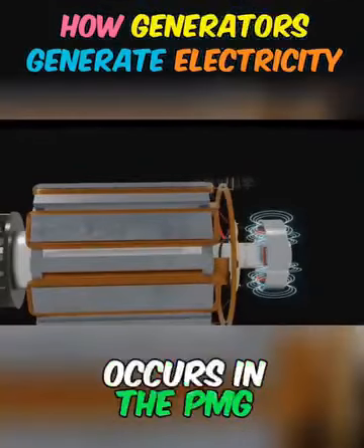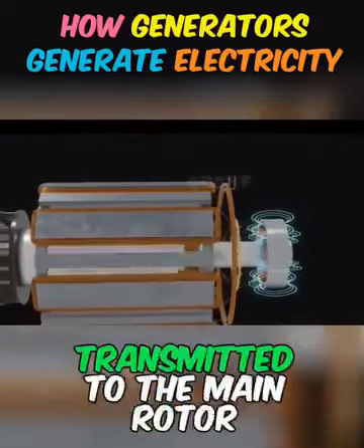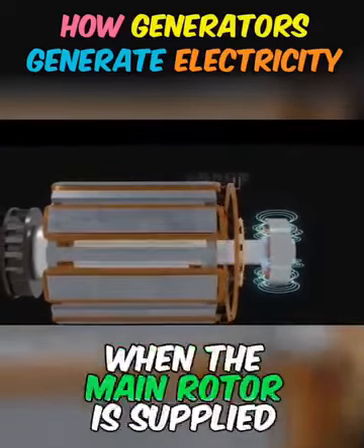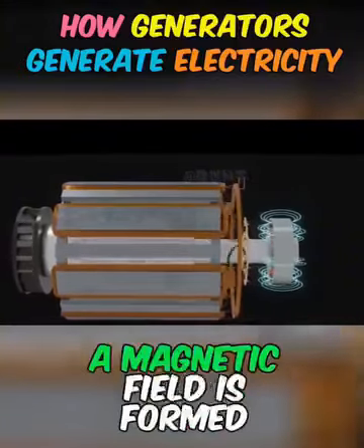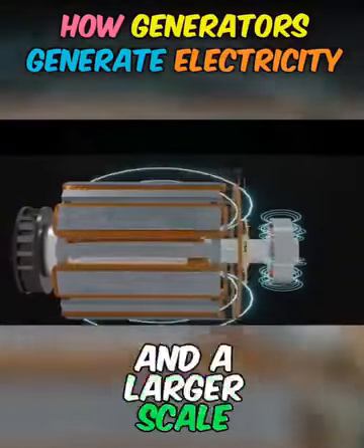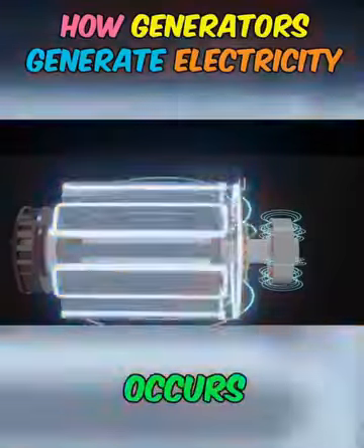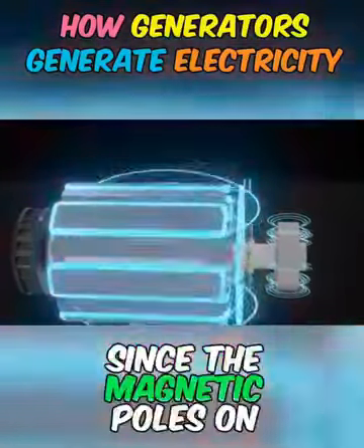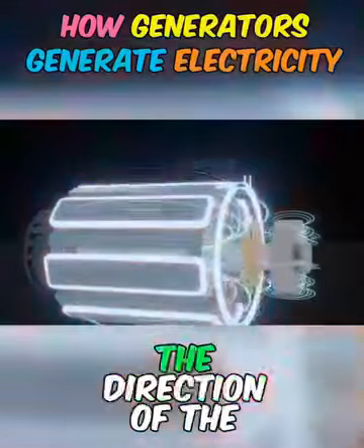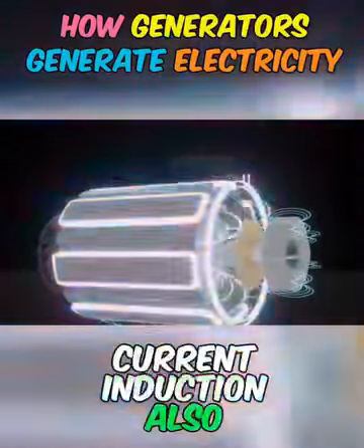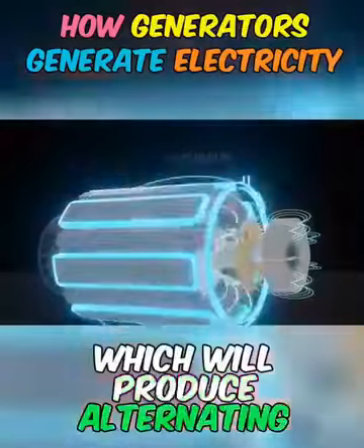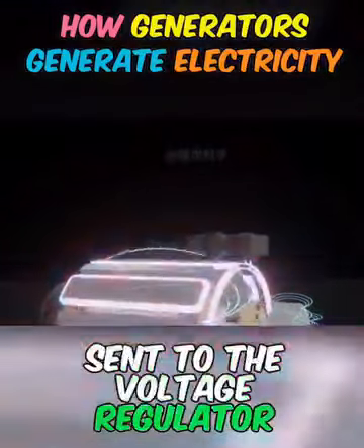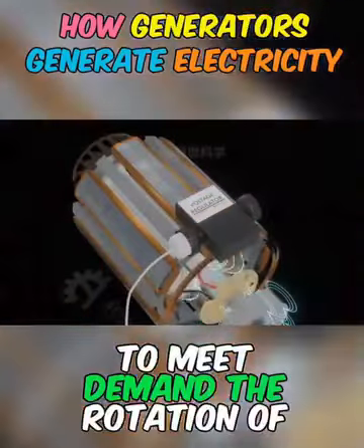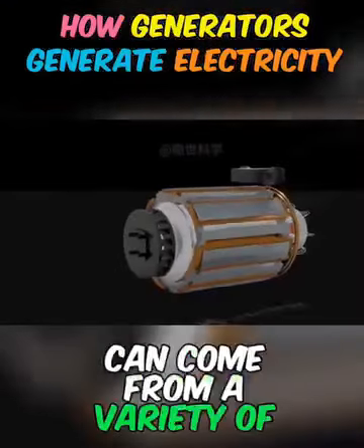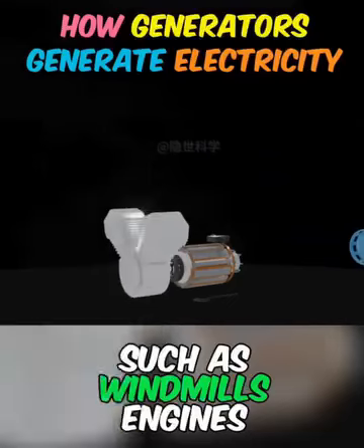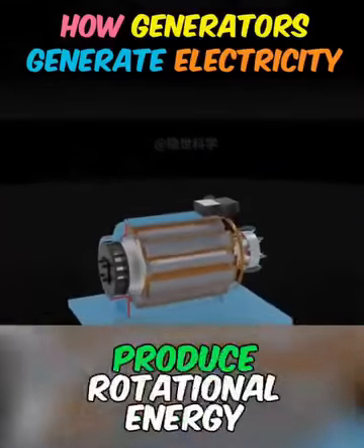When the generator rotor rotates, magnetic field cutting occurs in the PMG. The generated current is transmitted to the main rotor. When the main rotor is supplied with current, a magnetic field is formed, and a larger-scale magnetic field cutting occurs. Since the magnetic poles on the rotor are alternating, the direction of the current induction also alternates, which will produce alternating current sent to the voltage regulator for processing to meet demand. The rotation of the rotor can come from a variety of sources, such as windmills, engines, or other devices that produce rotational energy.